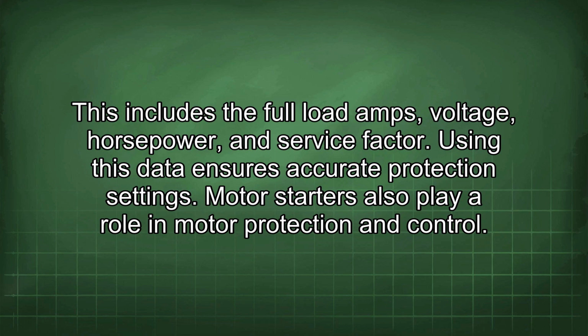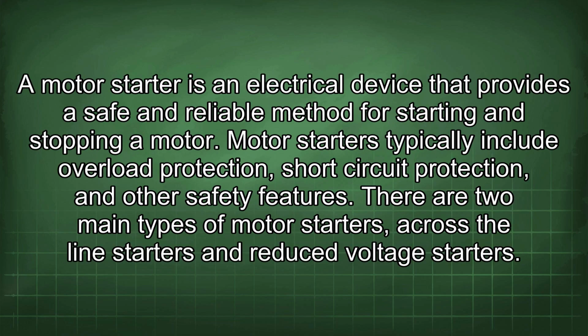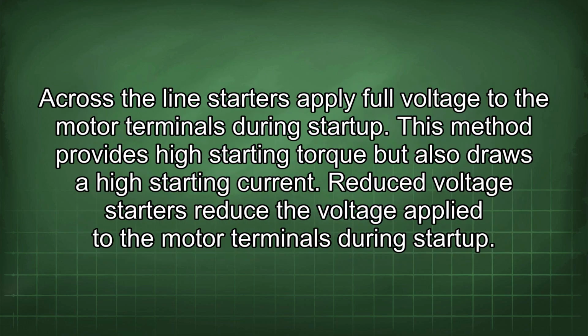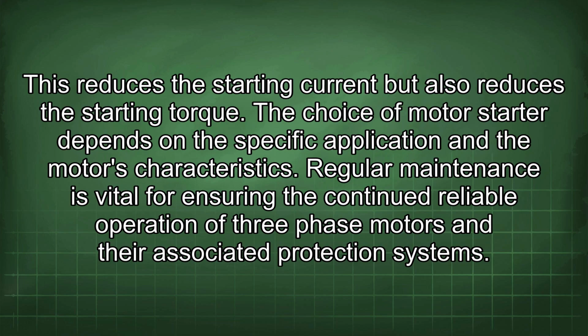Motor starters also play a role in motor protection and control. A motor starter is an electrical device that provides a safe and reliable method for starting and stopping a motor. Motor starters typically include overload protection, short-circuit protection, and other safety features. There are two main types of motor starters: across-the-line starters and reduced-voltage starters. Across-the-line starters apply full voltage to the motor terminals during startup. This method provides high starting torque but also draws a high starting current. Reduced voltage starters reduce the voltage applied to the motor terminals during startup. This reduces the starting current but also reduces the starting torque. The choice of motor starter depends on the specific application and the motor's characteristics.